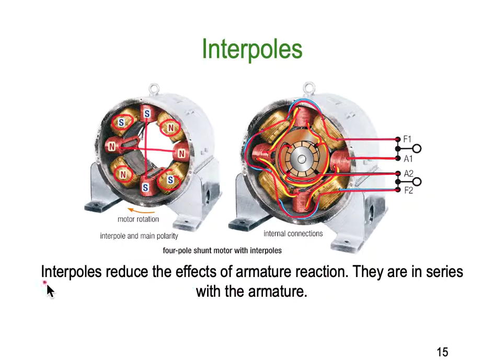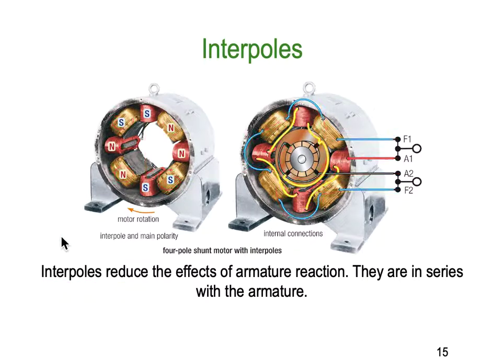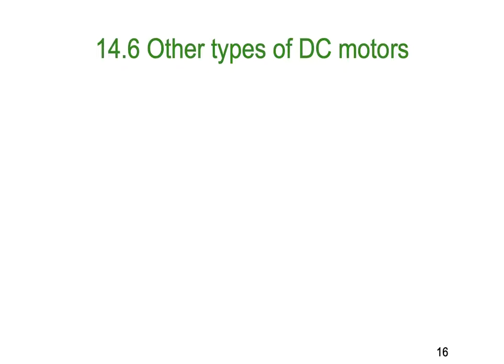So two ways we can reduce armature reaction: we can put in interpoles, and we can move the brushes a few degrees left or right to help. Putting in interpoles not only reduces armature reaction, it also gives you a much smoother mechanical output from your DC motor. That brings us to the end of control and operation of basic DC machines. We're now in section 14.6 — other types of DC motors.